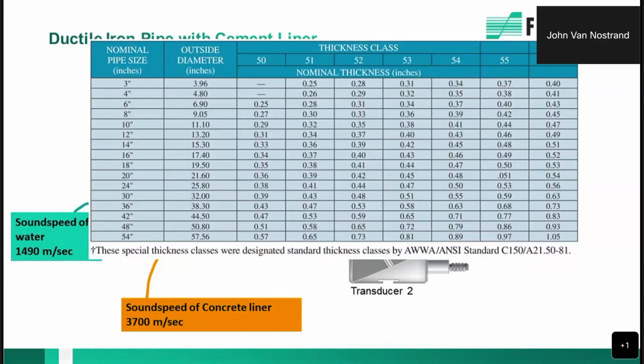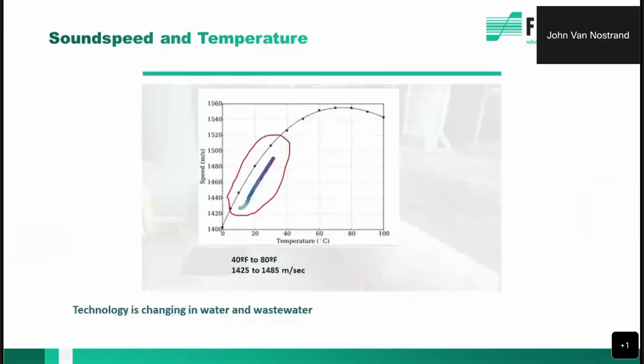Remember, I said the sound speed is what we're measuring, and we know that water at 70 degrees has a sound speed of about 1,490 meters per second. I look at that sound speed, and if it's not correct, I can back out of the wall thicknesses or go deeper into the wall thicknesses to ensure that I've got the right wall thickness programmed. I don't know anybody that goes on a ductile iron pipe and knows exactly what class it is. It's not marked. So you've got what you have, and you don't really necessarily know. With this meter, you can actually back into it and you'll know.